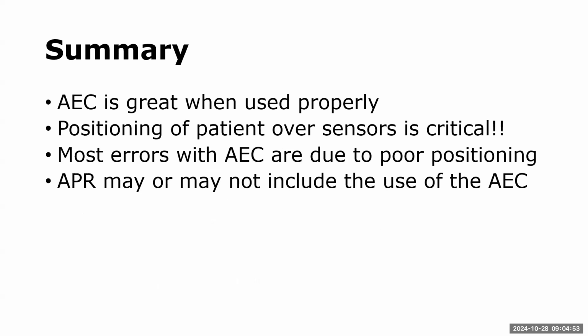Don't they have child settings? They may. It depends. Some of them will, and if it is a dedicated pediatric room, then those technique sets are going to be for peds. So let's say you brought an adult in there, you have to adjust it because those techniques are set for peds. Sometimes there'll be a little body part and a big body part setting that will adjust it some. But yes, it just depends on your equipment type.